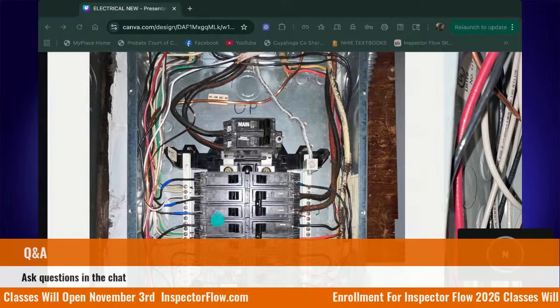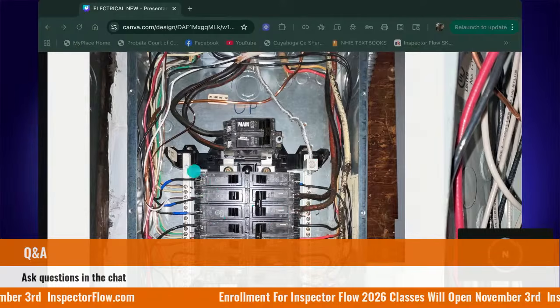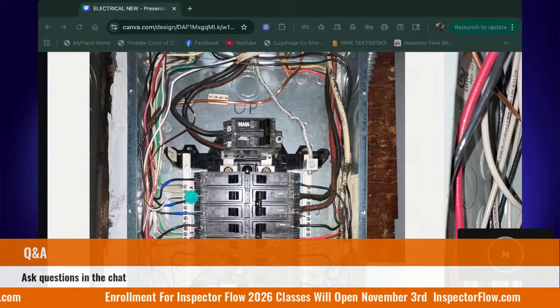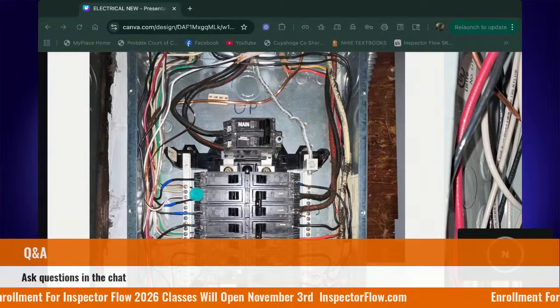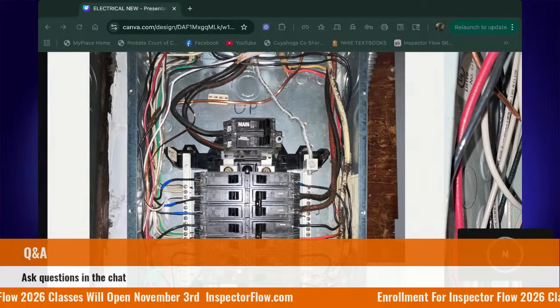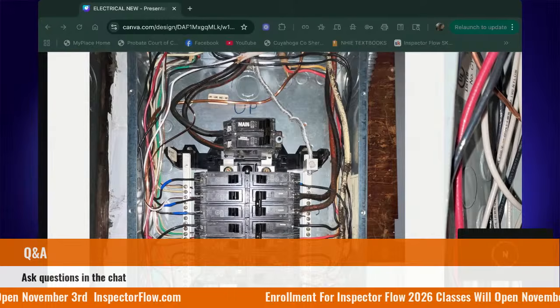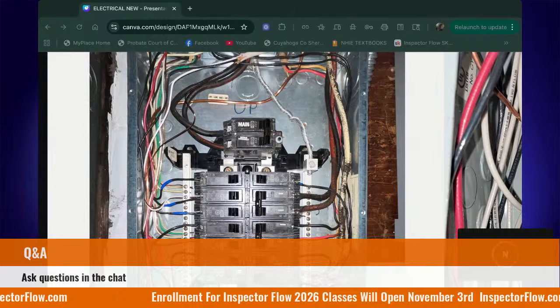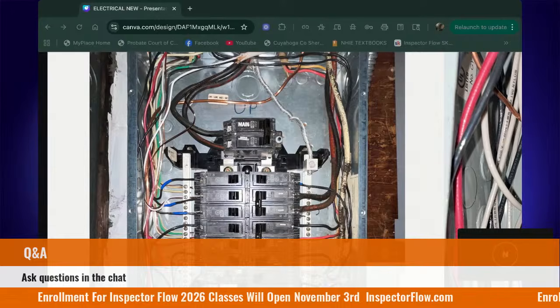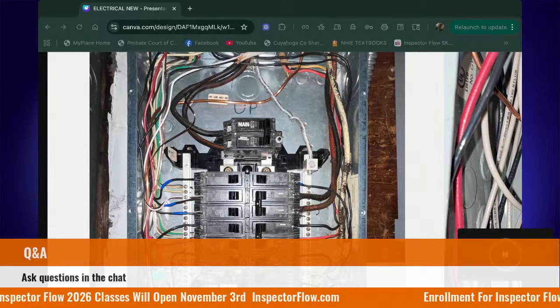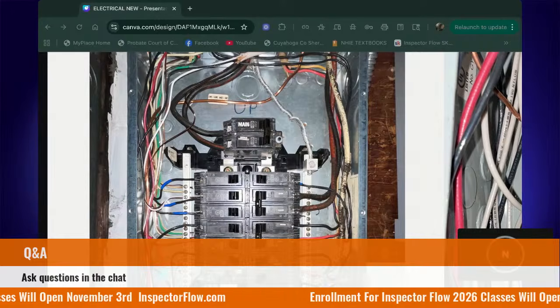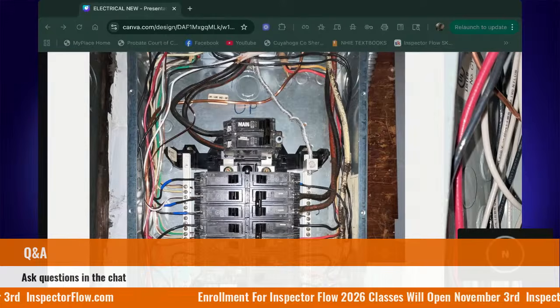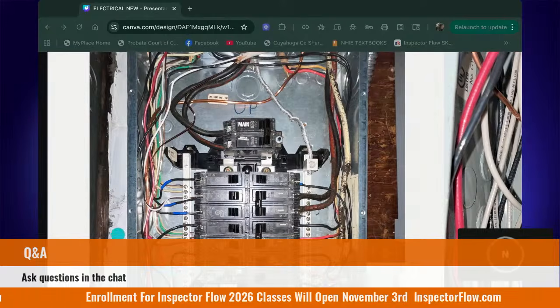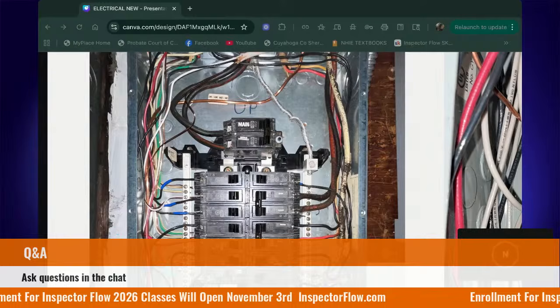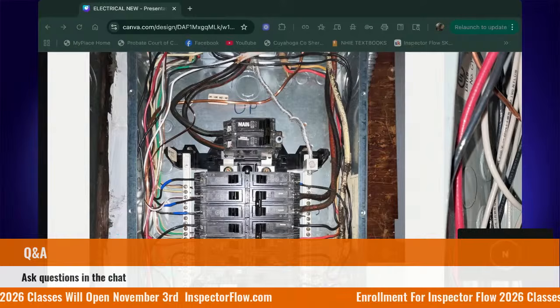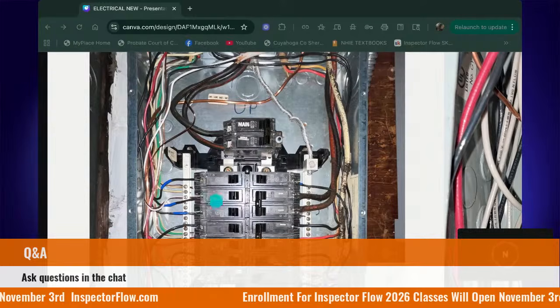And then we've got our different branch. So we've got a neutral grounding bus bar over here because I've got white wires as well as green wires. And see down here, that thick one? What is that? The copper, this should be the GEC. That is in fact the GEC. So it is terminating here. And then where is the other end connected to? The GE. That's correct.